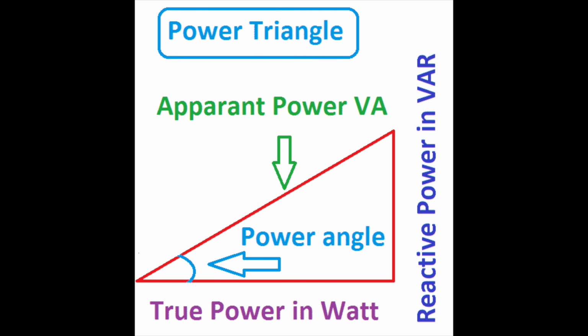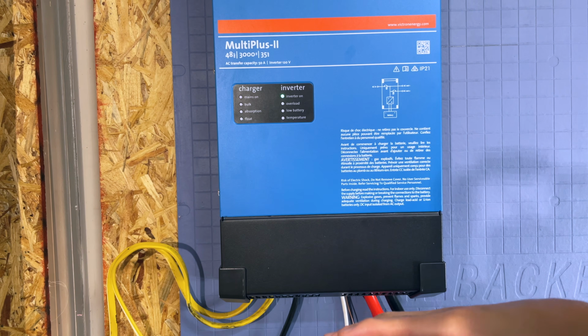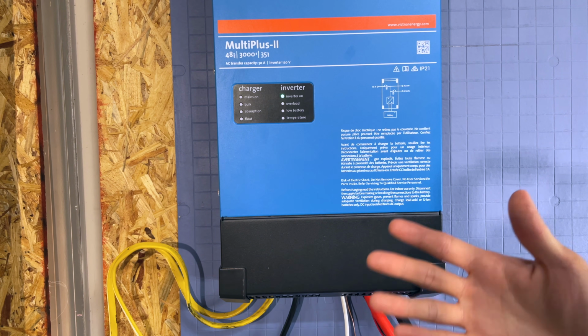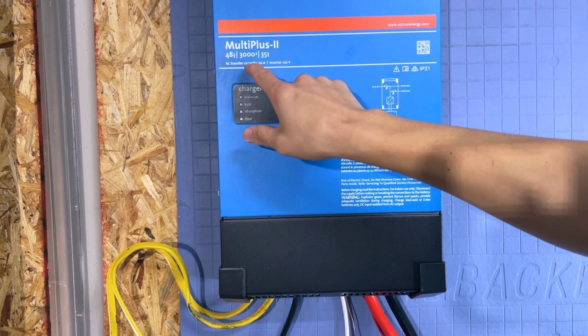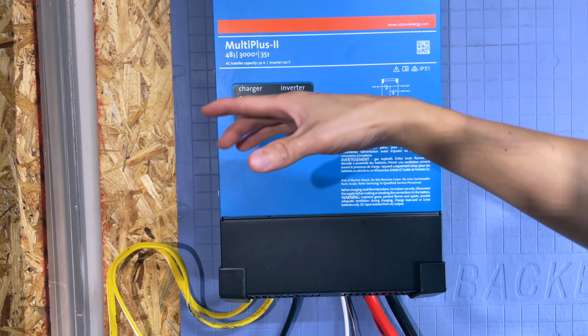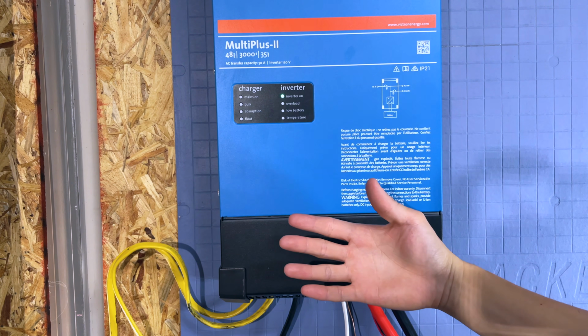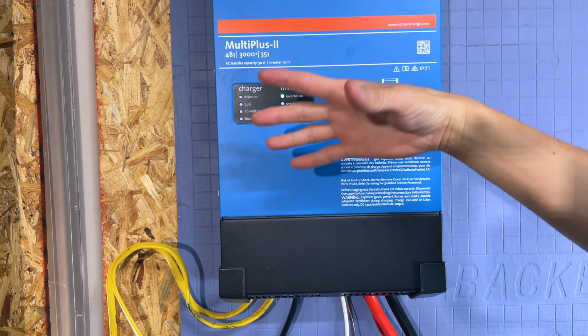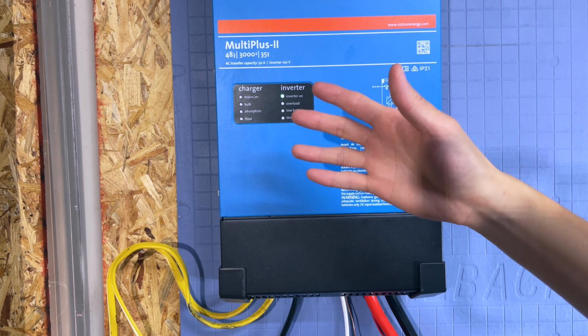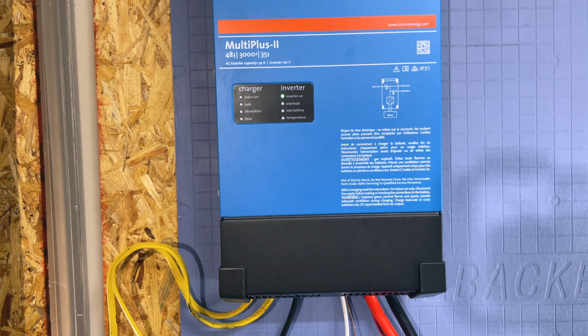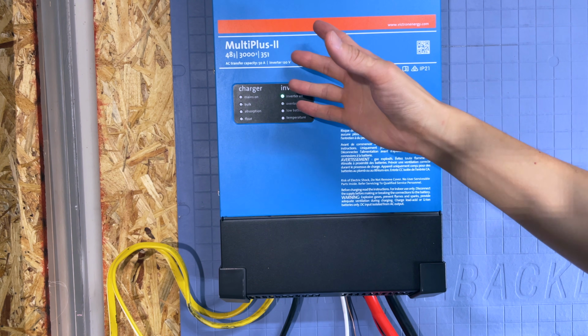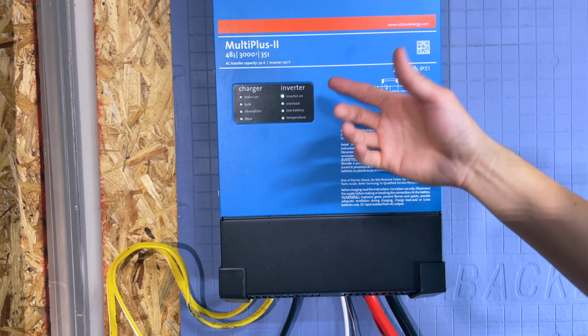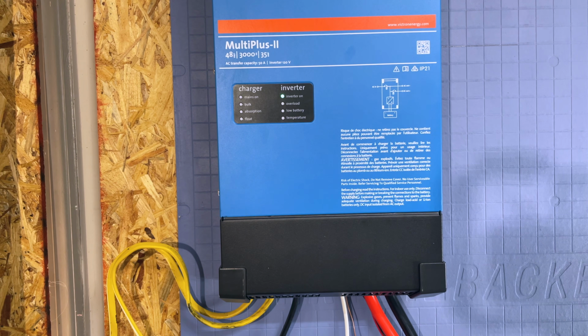To convert between the two, you take the apparent power and multiply it by the power factor to get the real power. That's generally how most people in the industry do it. So a 3000 VA system times, let's say, a power factor of 0.7 would give you your real power, which would be around 2400 watts or so. If your power factor is 0.8, then 3000 times 0.8 is how you'd get watts. But let's talk about that.